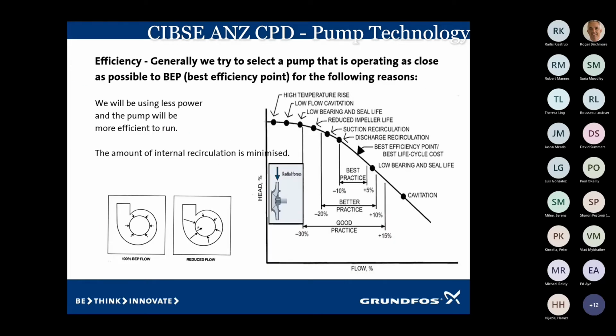If we look at our efficiency curve and our best efficiency and our pump curve, this is a really good graph to indicate what's actually happening inside the pump. And this is why we try to always select the pump around its best efficiency area. Good practice, or better practice, is minus 20 to plus 10% in and above the best efficiency area. It's not always possible. Sometimes we get stuck. We end up having to select a pump sitting in another part of the curve, higher up or further down. But this is a really good guideline.